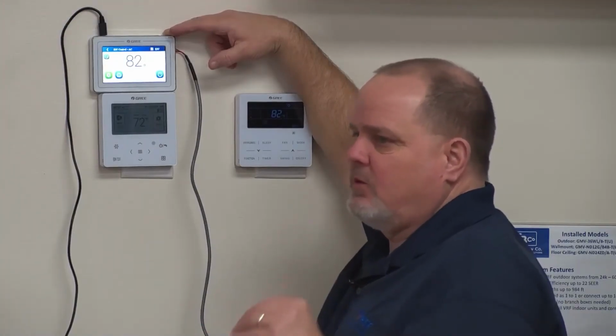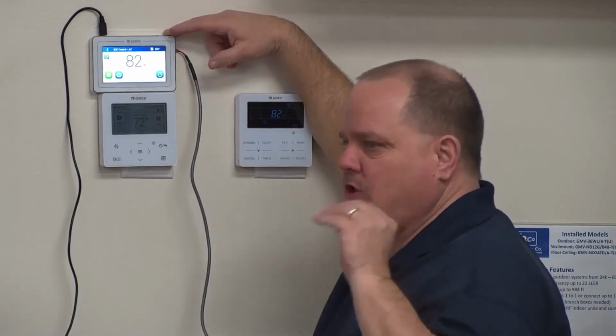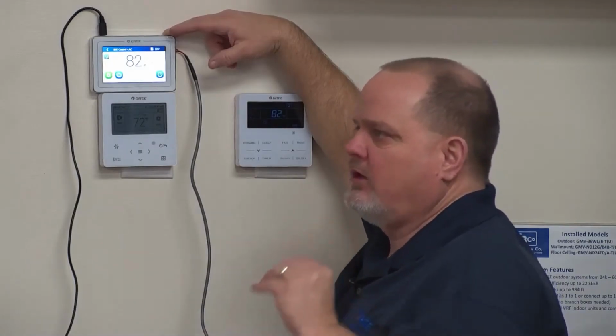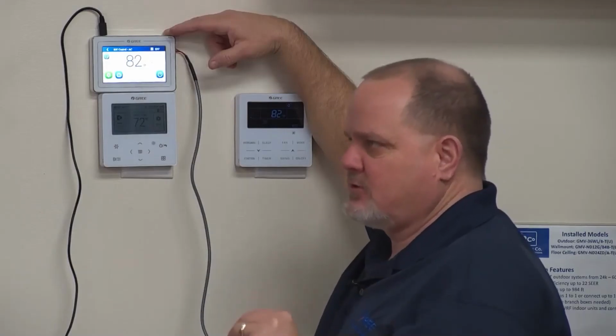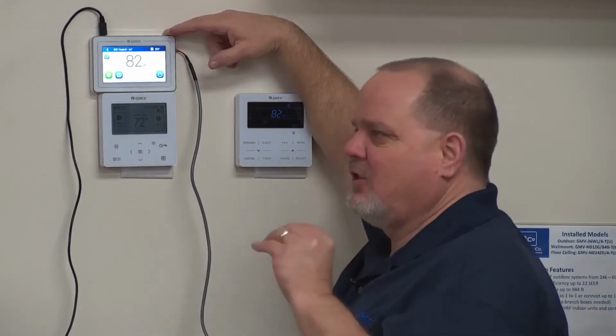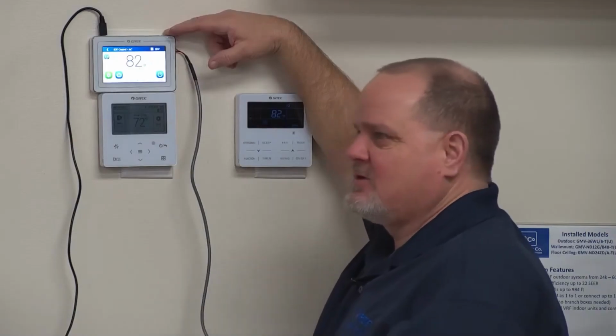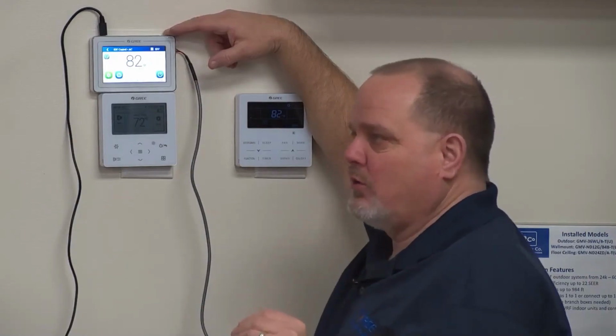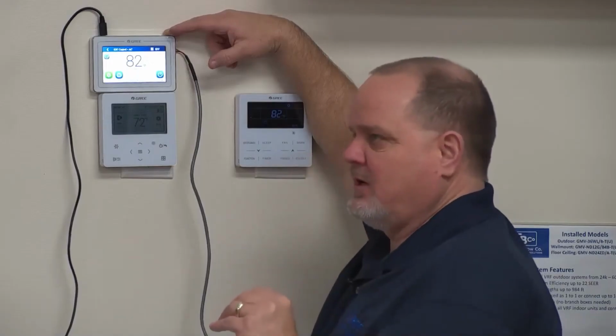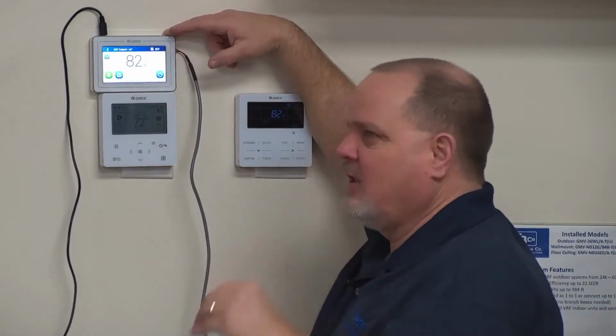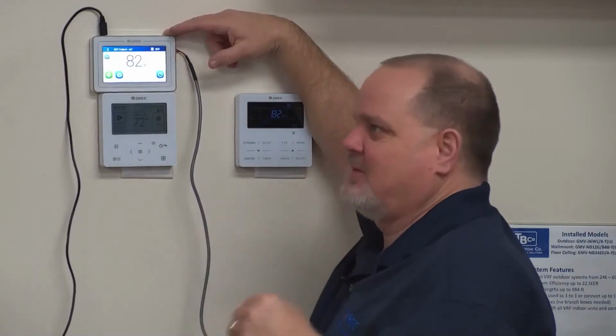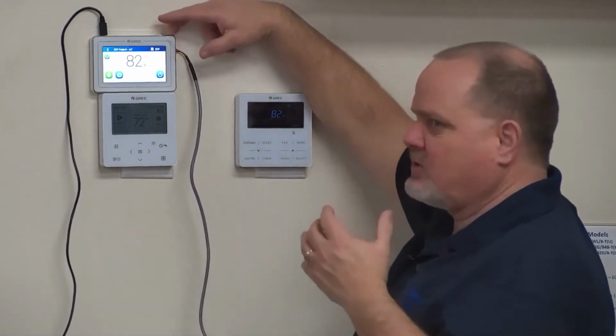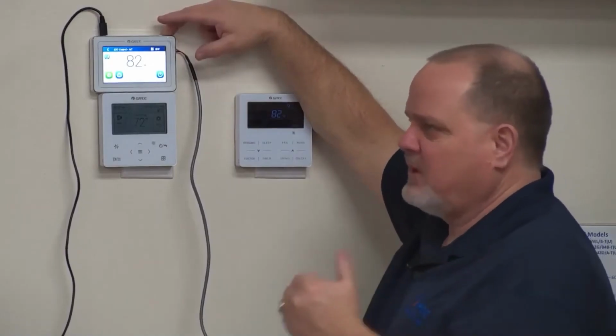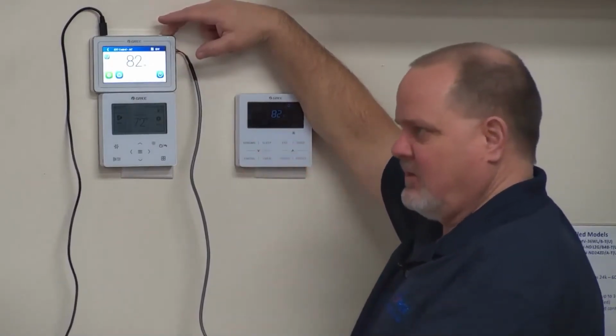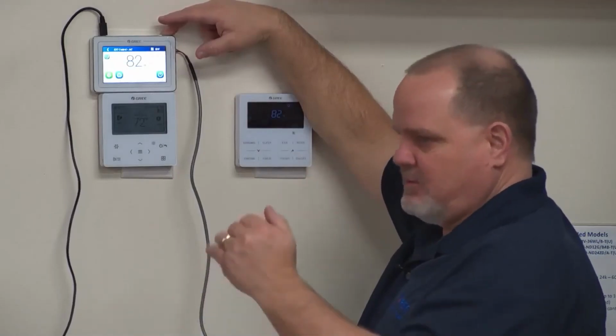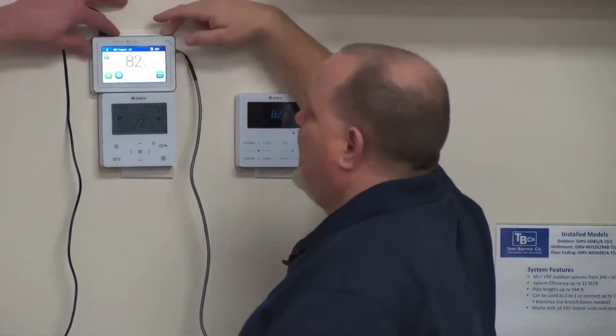The way variable speed works on these is it will adjust the blower speed according to the inlet and outlet temperature sensors and the EEV step and the load that's on the machine. So if you have very little load, you're going to have a lower blower speed. If you have a very high load, then you're going to have a higher blower speed. So I just want people to understand what variable speed really means in inverter-driven equipment, especially MultiPRO. Okay? All right, so now we're running.